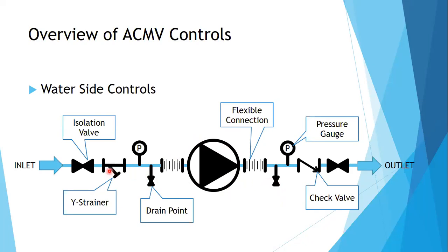Wye strainer to ensure that there's no debris going to your pump. This debris, even though small, tends to destroy or damage your pump. So that's why the wye strainers are important. That's why pipe flushing is important within your pipe installation. And last one is your check valve to ensure that there's only one way flow. There's no backflow of any fluid to the pump. It will damage your pump. Backflow will damage your pump.